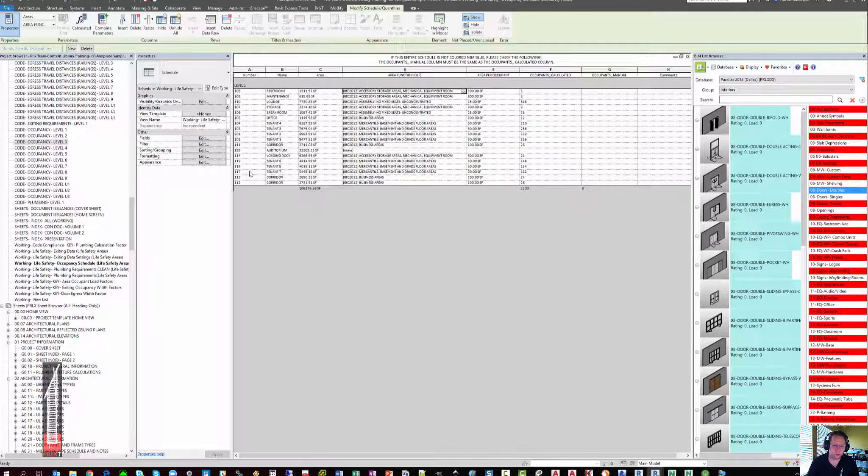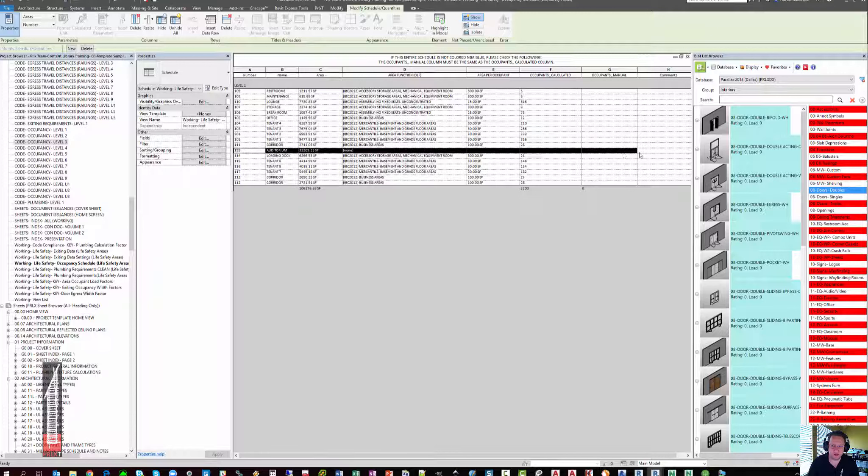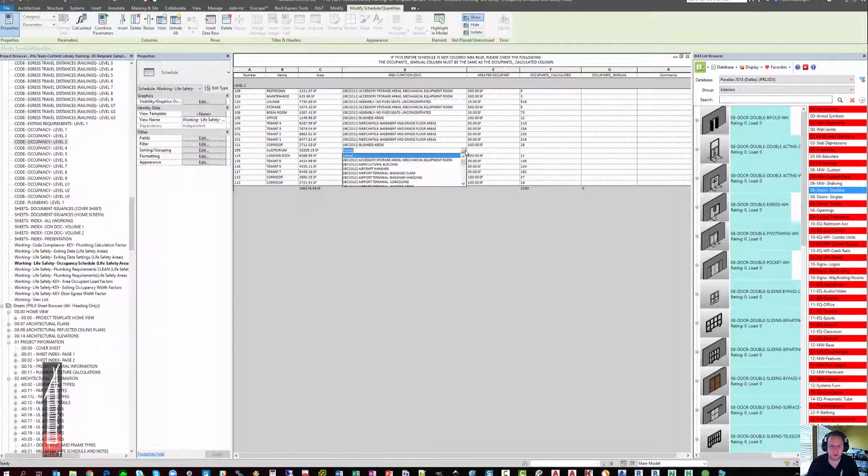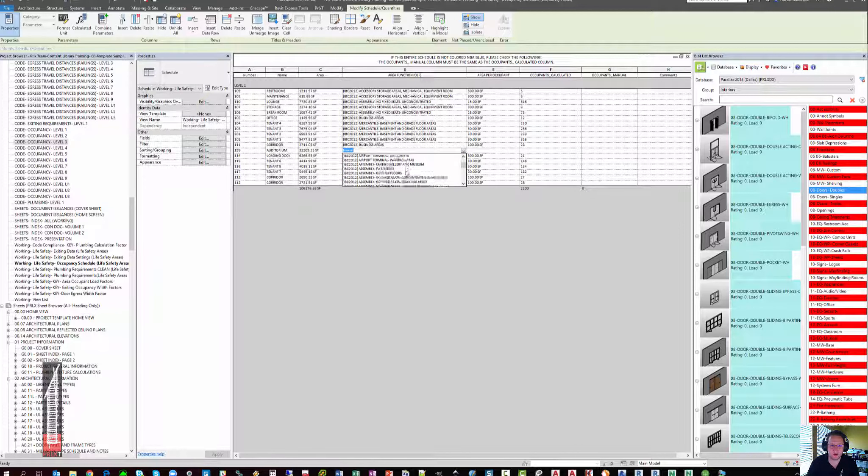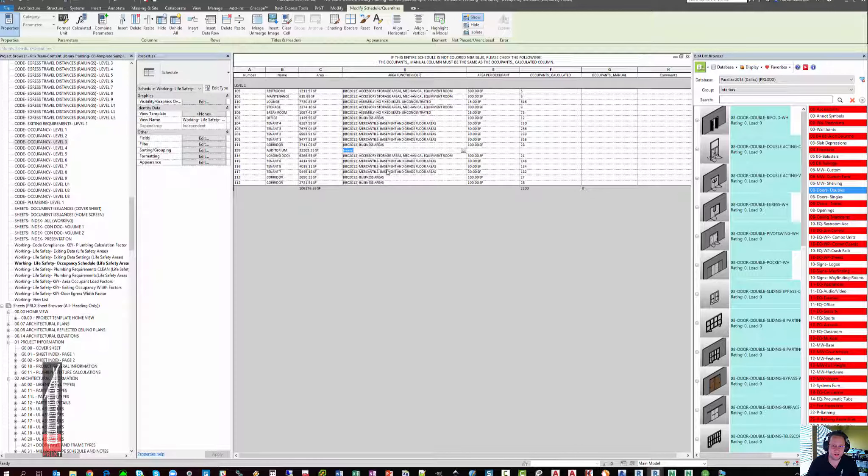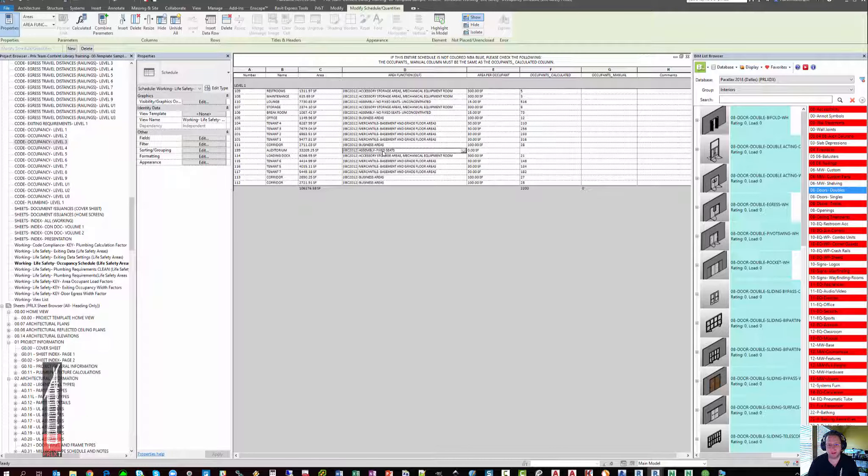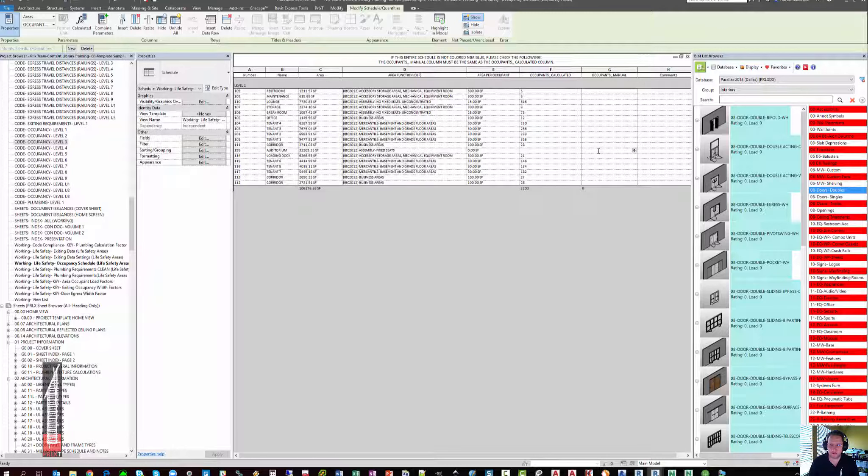One particular item of note is that you may have spaces that have fixed seating. This may be things like movie theaters or auditoriums or other assembly spaces. As the code calls for assemblies with fixed seats to have the occupancy based on the number of fixed seats in the area, you can actually pick assembly fixed seats and then you can type in the number of seats in a later schedule.